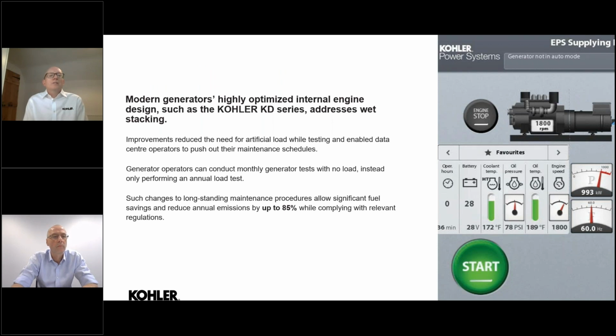So, as we said, modern generators have highly optimized internal engine designs, which you'll see in our KD series, but this also addresses something called wet stacking. So improvements reduce the need for artificial load while testing and enable data center operators to push out their maintenance schedules. Generator operators can conduct monthly generator tests now with no load instead of only performing an annual load test. These changes to the long-standing maintenance procedures allow significant fuel savings and reduce annual emissions by up to 85%, while complying, of course, to the relevant regulations.